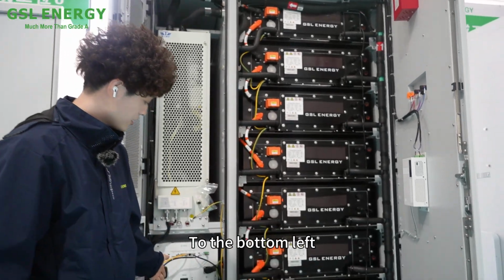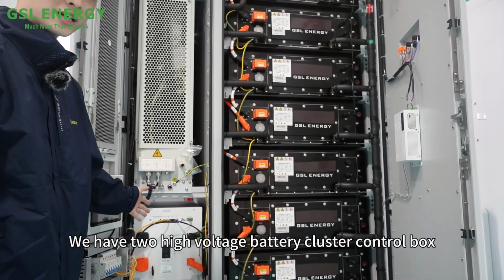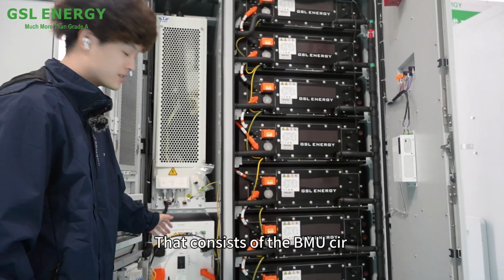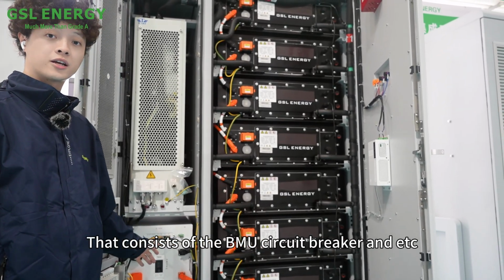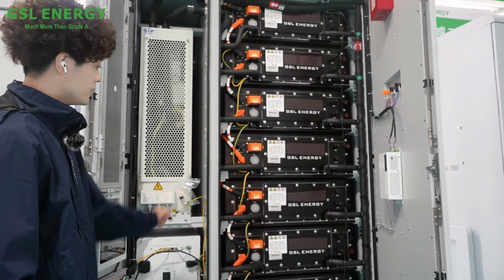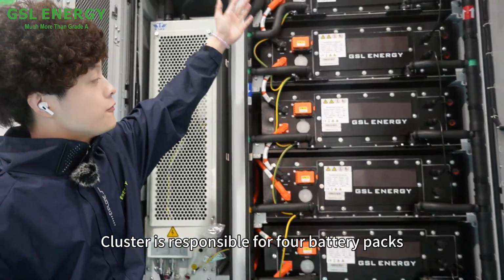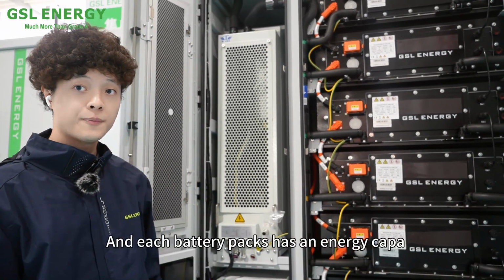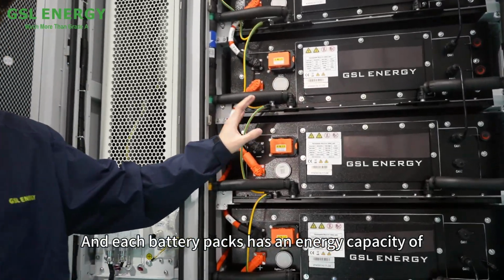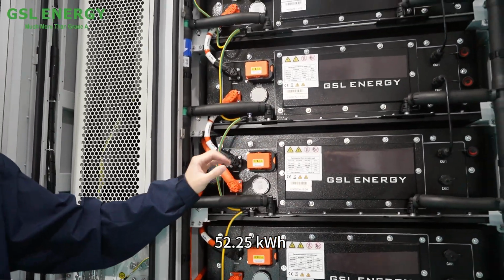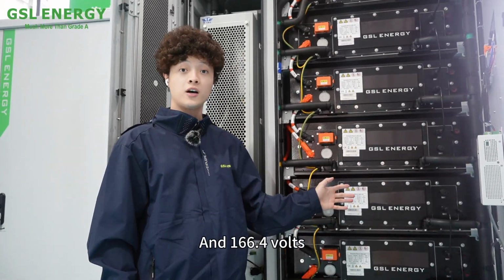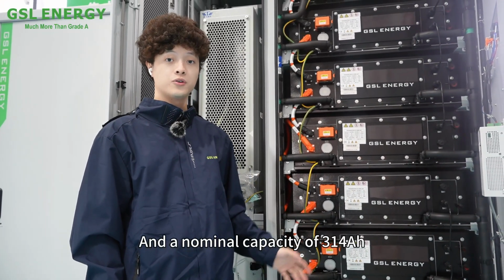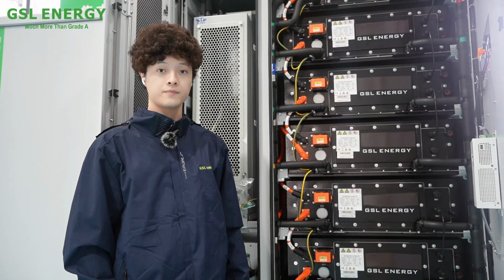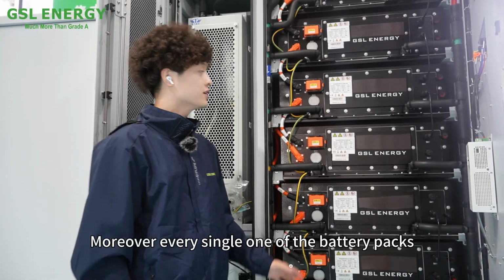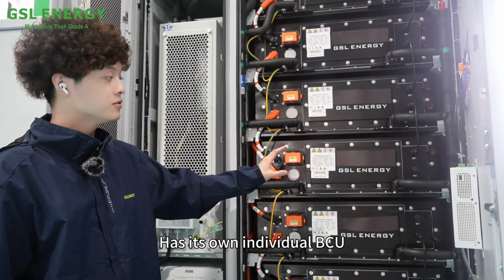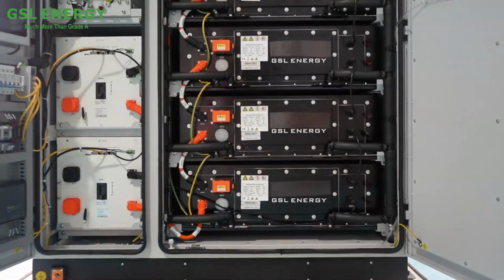To the bottom left, we have two high voltage battery cluster control blocks that consist of the BMU, circuit breaker, and etc. Each battery cluster is responsible for 4 battery packs, and each battery pack has an energy capacity of 52.25 kilowatt hour and 166.4 volts, with a nominal capacity of 314 ampere hour. Moreover, every single one of the battery packs has its own individual BCU.